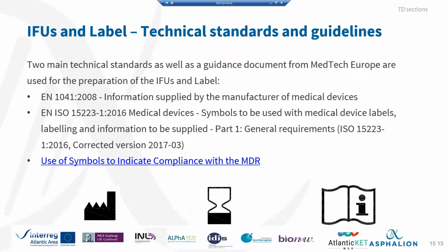So usually what you do is follow these standards when preparing both the instructions for use and the label. There are also guidance documents from MedTech Europe, which you have the link to here, which indicate which symbols should be used to indicate compliance with the medical devices regulation.